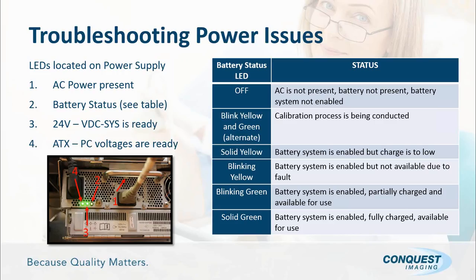And a side note, while we're talking about the batteries: if the system is shipped to you brand new, you probably won't have to worry about it because it's being installed by Philips. But if it's not brand new and you're getting it shipped to, say, a separate facility, there are 2 batteries in it, and they should be taken out, turned upside down, and put back in the slots located at the bottom there. You can see the slot right there. There are 2 batteries, 2 slots, but they should not remain engaged. So they simply tell you to pull them out, turn them upside down, and put them back in during shipment. Also, if you're replacing the batteries, be sure that you replace them as a pair. That's right out of the manuals, and it's a really important concept. Don't replace one without replacing the other.